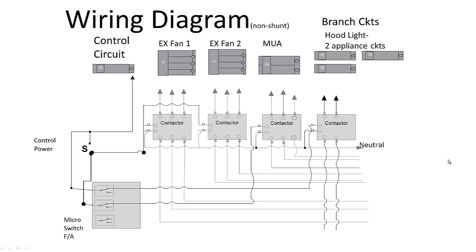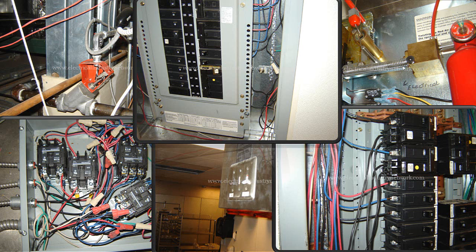Now I'm going to pop into this other page — this is the Ansul system I've got some pictures of. There are your micro switches in an Ansul system. That is a shunt trip breaker up there, even though that's not part of the wiring diagram I just showed you. There's also a gas valve — this particular one is a mechanical gas valve; I have run into some electric gas valves before, though they're not as common. And here are somebody else's coils and contactors wired in with the shunt trip system.